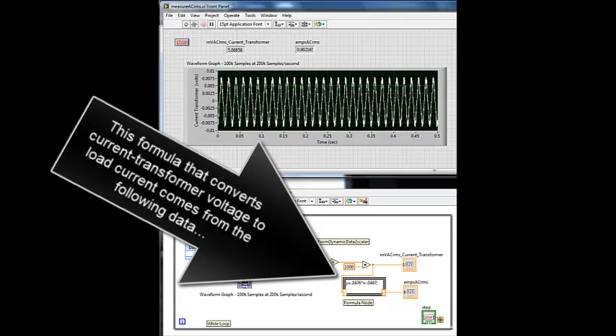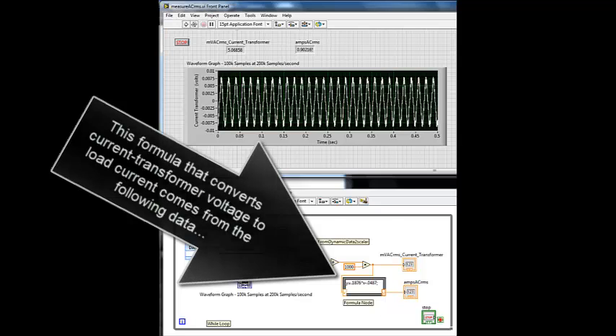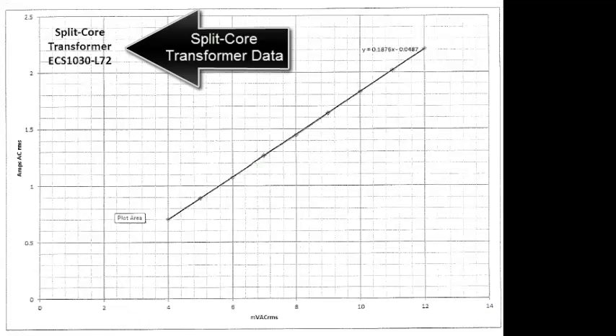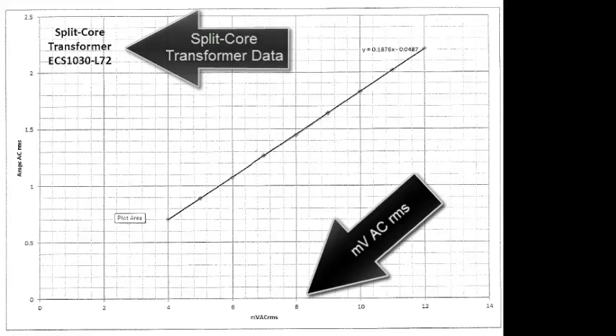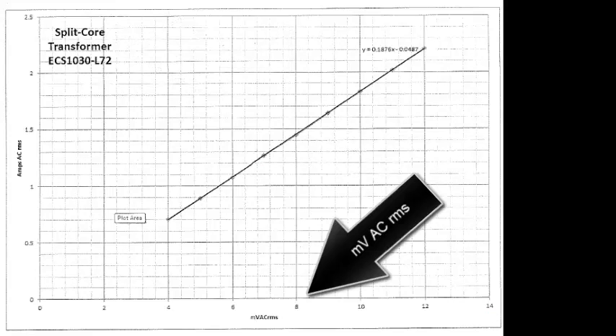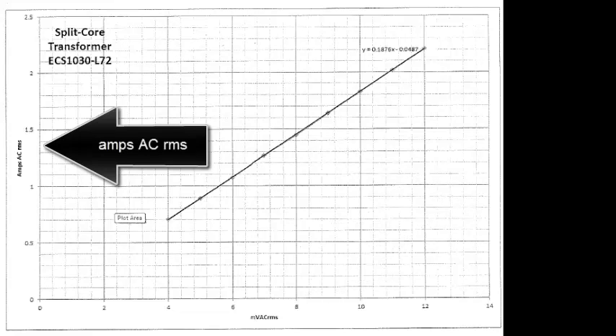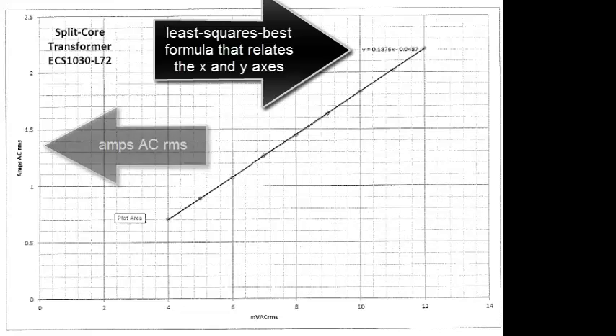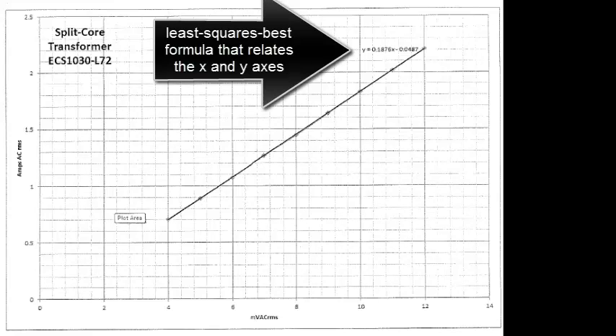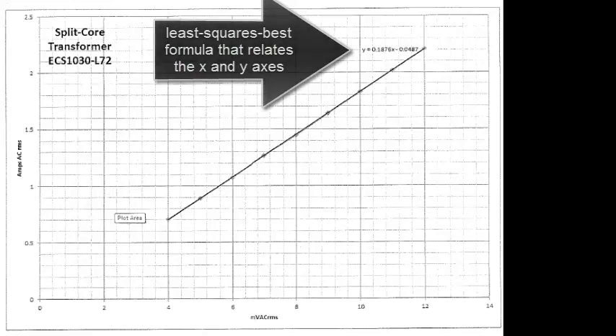This formula that converts current transformer voltage to load current comes from the following data. This is for the split-core transformer. The horizontal axis is millivolts AC RMS. The vertical axis is amps AC RMS. And that's the least squares best formula that relates the X and Y axes.